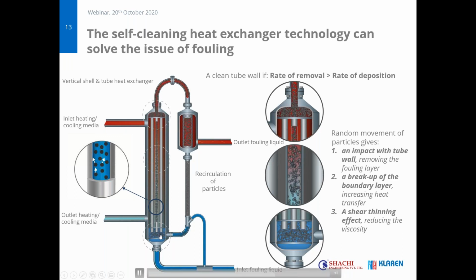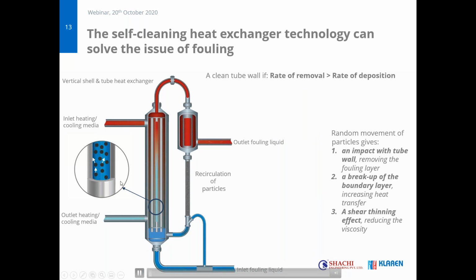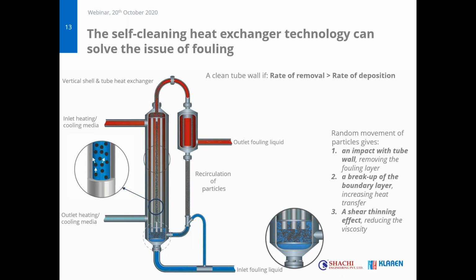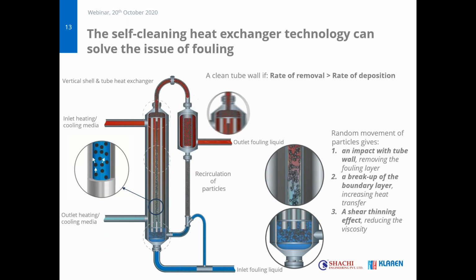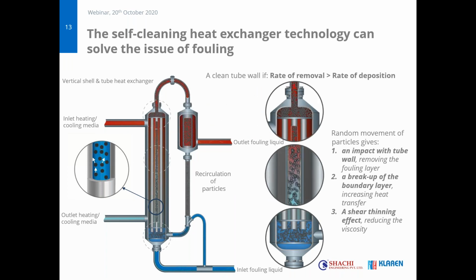These particles are taken with the flow upwards through the heat exchanger tubes. If you would zoom into such a tube, you would see those particles moving in a chaotic manner. In this chaotic manner, they impact each other, but they also impact the tube wall. And by these small impacts of the cleaning particles with the tube wall, we create a scouring action on the wall, which removes a layer that wants to develop.